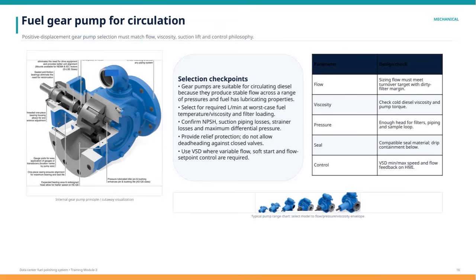Let's talk about the fuel gear pump used for circulation in our system. The key to selecting a positive displacement gear pump is ensuring it matches the required flow rate, fuel viscosity, suction lift, and the overall control philosophy of the system. Gear pumps are especially well suited for circulating diesel because they provide a stable flow even as pressure varies, and diesel fuel's natural lubricating properties help the pump operate efficiently.